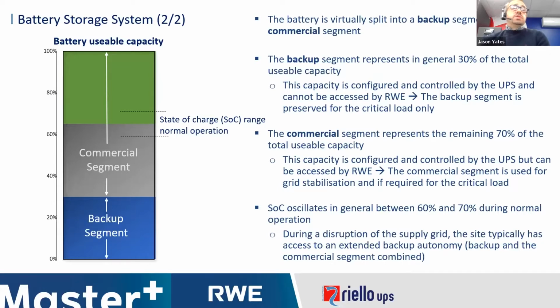The remaining segment of the battery was the commercial segment. The commercial segment represented the remaining 70% of the total usable capacity. Again, this capacity was configured and controlled by the UPS, but this time only RWE had access to this section, and therefore the commercial segment is used for grid stabilization and, if required, for the critical load. Typically, when the system is operating, the state of charge of the battery, as you can see there, generally oscillates somewhere between 60 and 70%. Therefore, if there was a main supply failure on the site where this system is installed, the site will typically have access to an extended backup autonomy, because they have the use of their guaranteed backup segment plus any of the remaining commercial segment.